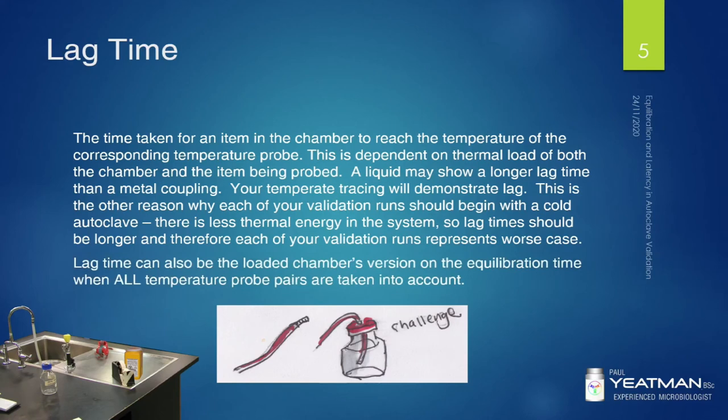Lag time can also be the loaded chamber's version of the equilibration time, when all temperature probe pairs are taken into account — so you've got a probe next to something you want to check the temperature of, and a probe inside what you want to check the temperature of, which is demonstrated by the sketch on screen.